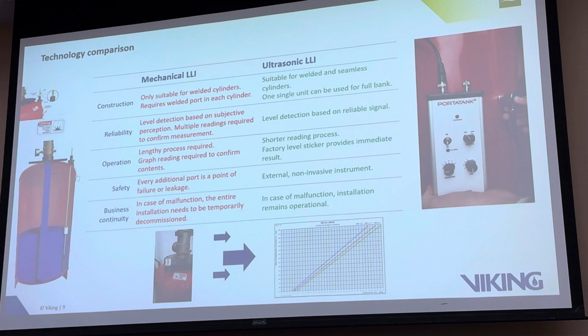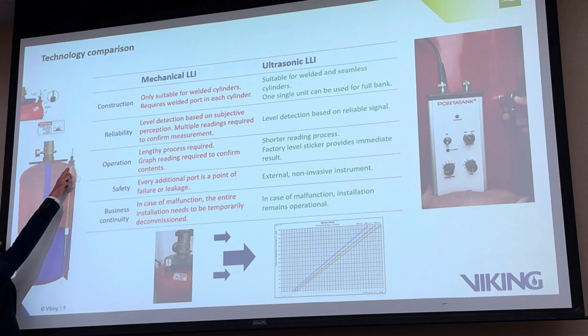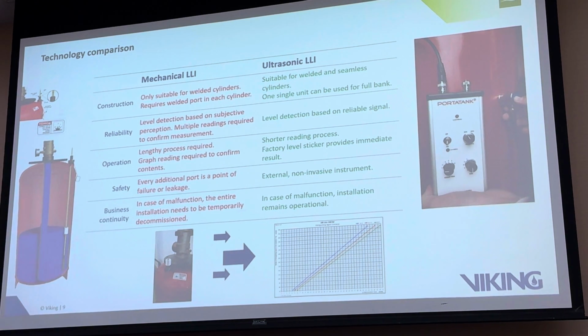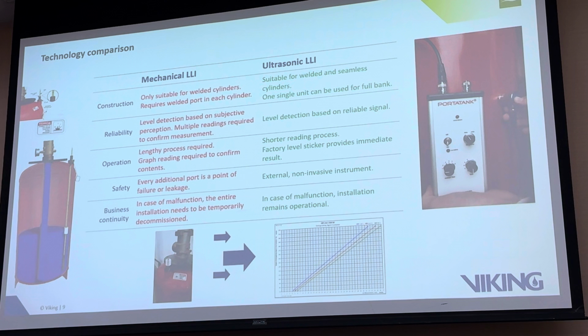So, a quick comparison between the mechanical liquid level indicator and the ultrasonic liquid level indicator, the pros and cons. On construction: the mechanical is only suitable for welded cylinders, because it requires a port which has to be welded, and if the cylinder is welded it cannot work at more than 25 bar, 42 is already too much for a welded cylinder. The ultrasonic liquid level indicator works with both seamless and welded cylinders, so you can work with 42 or 50 bar systems with no problem.